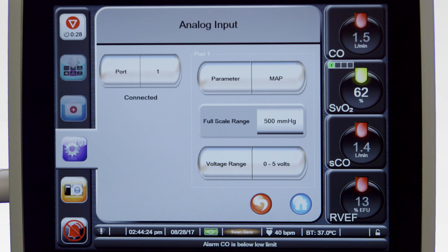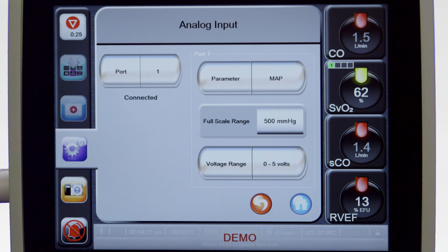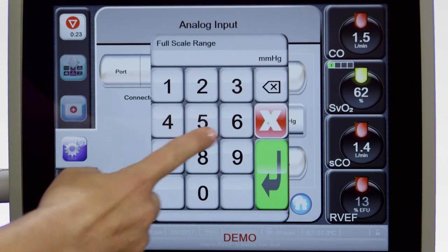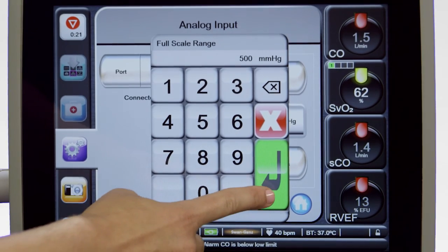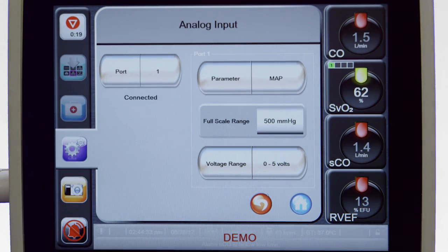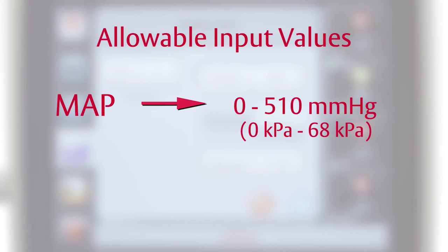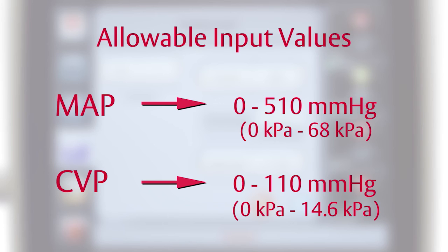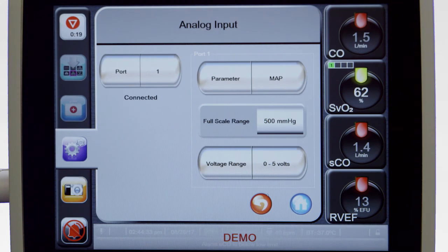Touch the Full Scale Range Value button to change the displayed full-scale signal value. The allowable input values for full-scale range for MAP and CVP are 0 to 510 mm Mercury and 0 to 110 mm Mercury, respectively. A voltage reading of 0 is automatically set to a minimum pressure reading of 0 mm Mercury. The full-scale range represents the full-scale signal or maximum pressure reading for the selected voltage range.